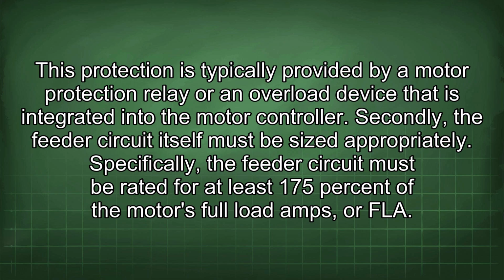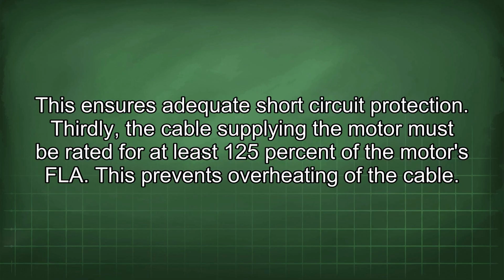Specifically, the feeder circuit must be rated for at least 175% of the motor's full load amps, or FLA. This ensures adequate short-circuit protection. Thirdly, a cable supplying the motor must be rated for at least 125% of the motor's FLA. This prevents overheating of the cable.